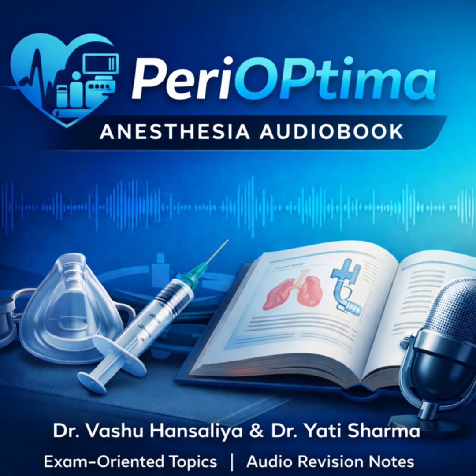A hypoxic gas mixture. You failed to turn on the oxygen cylinder. There's a disconnect in the breathing circuit. Or, and this is more historic but still important, a failure of the hypoxic guard on an older anesthesia machine. Right. High altitude is nature. A hypoxic mixture is negligence. Okay, what's the second cause?